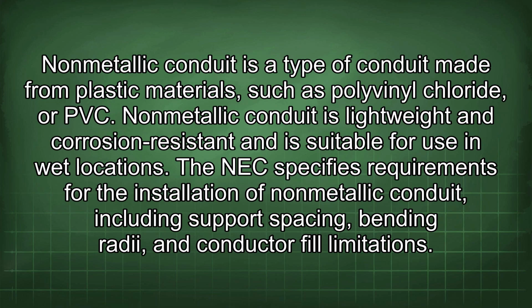Non-metallic conduit is a type of conduit made from plastic materials such as polyvinyl chloride, or PVC. Non-metallic conduit is lightweight and corrosion resistant and is suitable for use in wet locations. The NEC specifies requirements for the installation of non-metallic conduit, including support spacing, bending radii, and conductor fill limitations.